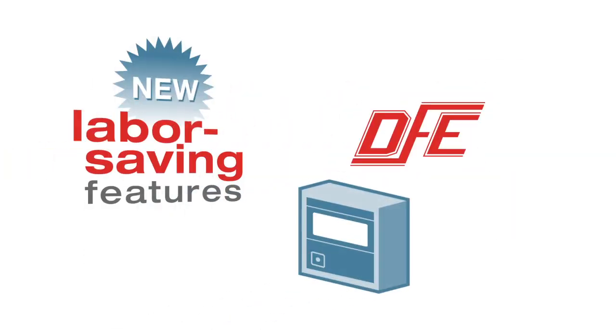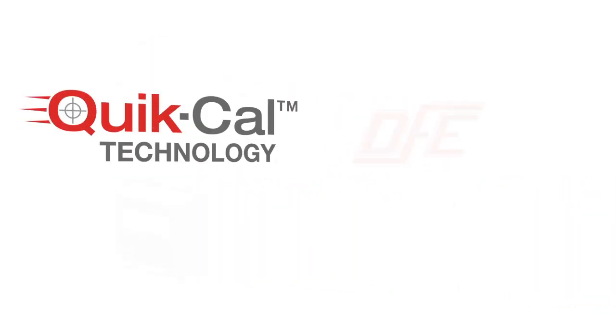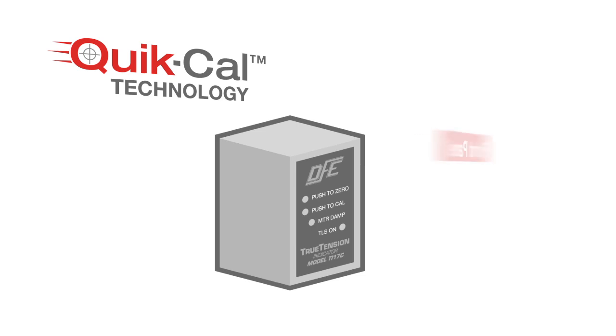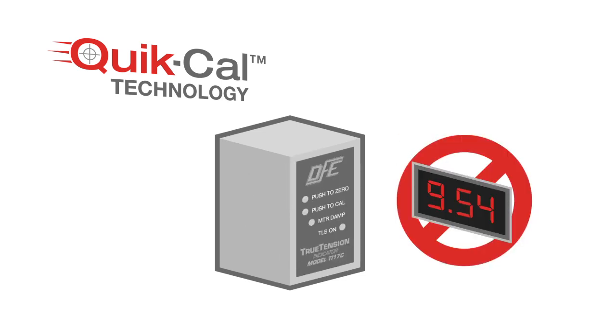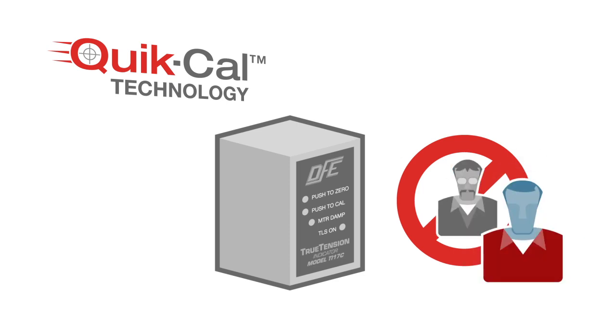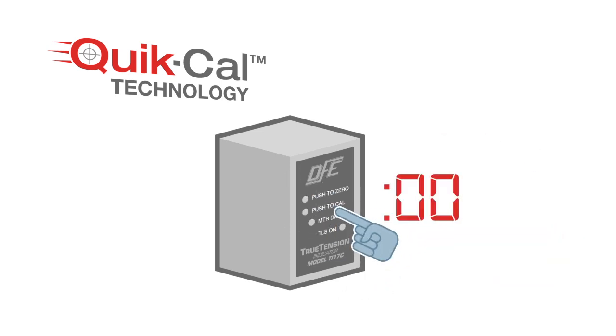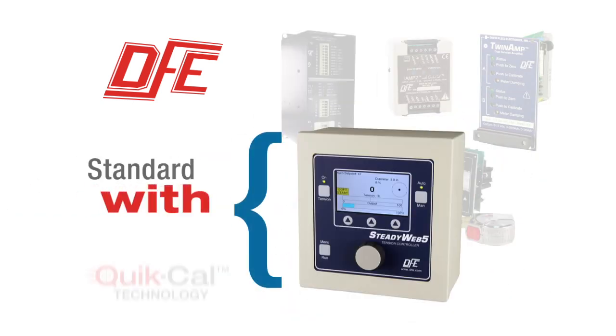One of the new labor-saving features of DFE's tension indicator and controller products is Quik-Cal technology. With Quik-Cal, the indication and control electronics use front panel push buttons instead of potentiometers for zero and calibration settings. No tension display is needed, no screwdriver is needed, no second person is needed. Each button is pressed once during the calibration procedure for one second, and the settings are stored automatically. Most of DFE's newer amplifiers, indicators, and tension controllers come standard with Quik-Cal.